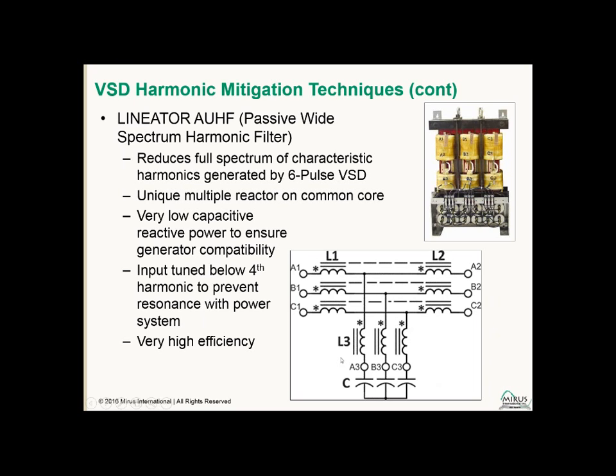We've designed it to have very, very low capacitive reactive power to make it compatible with generators. So even at no load conditions, the reactive power of the filter is less than 15% of the rated power of the variable speed drive. So this ensures compatibility with the generator. We're also tuned below the 4th harmonic so that we won't attract harmonics from the power system into the filter. The predominant harmonics in the power system are 5th and above, and so we're tuned below that so that we do not attract those harmonics. And we're the highest efficiency of all solutions available for variable speed drive applications.